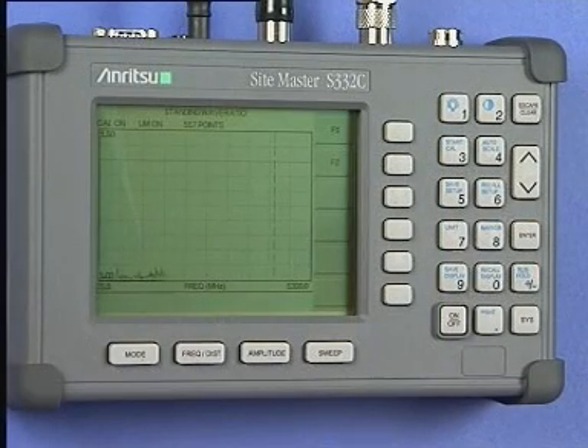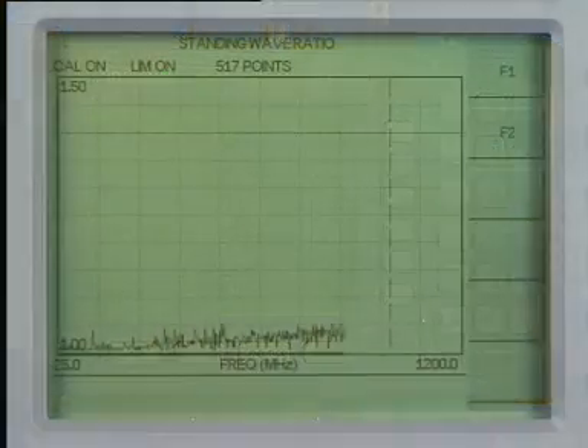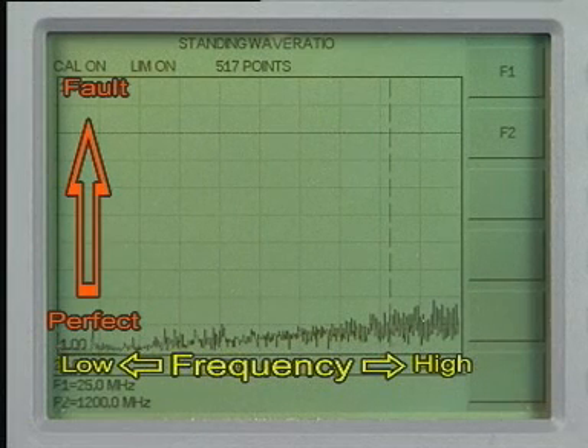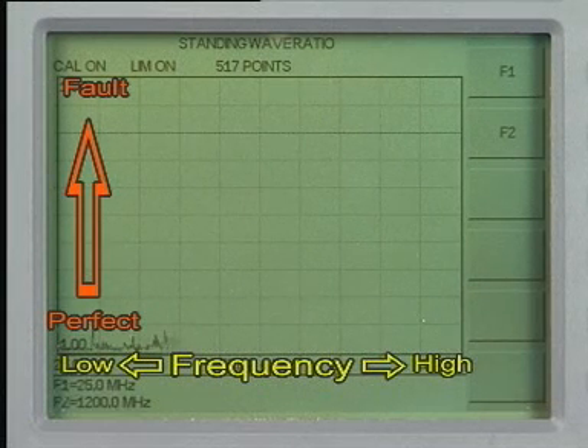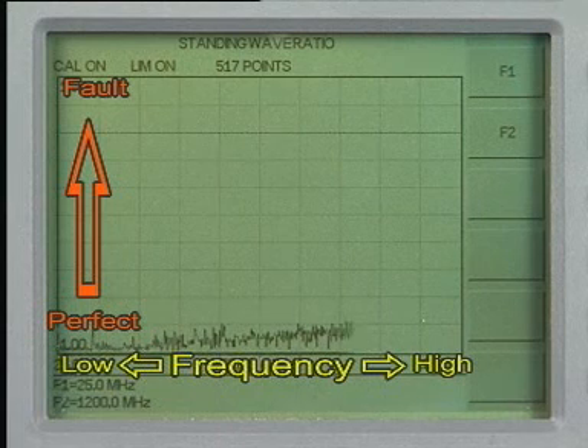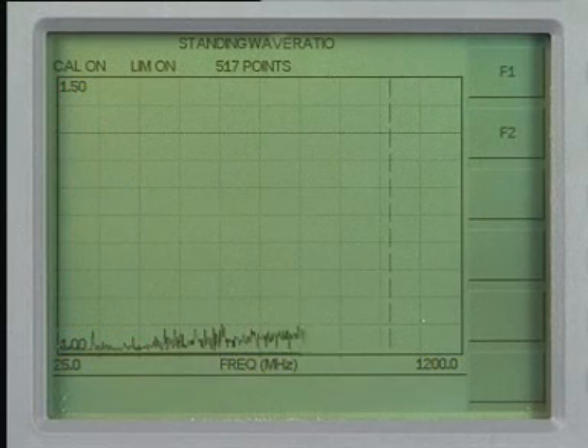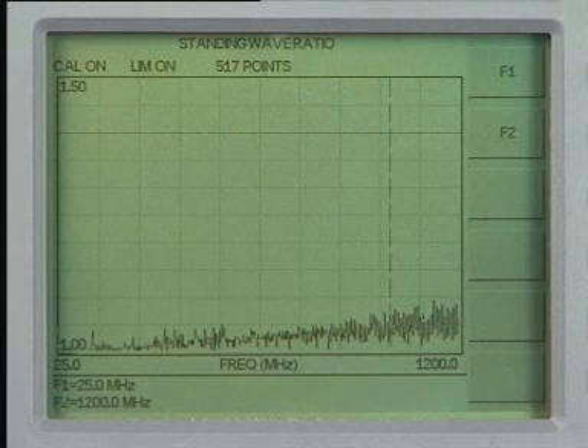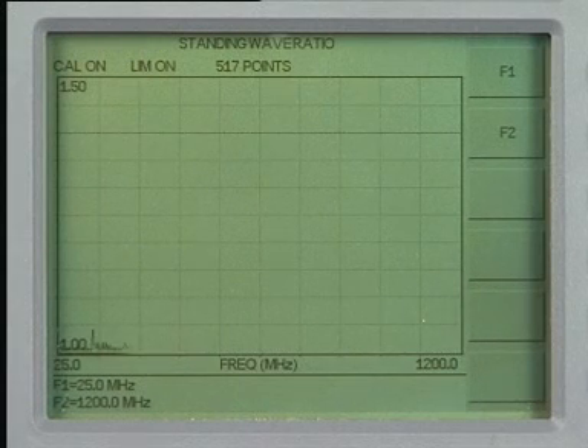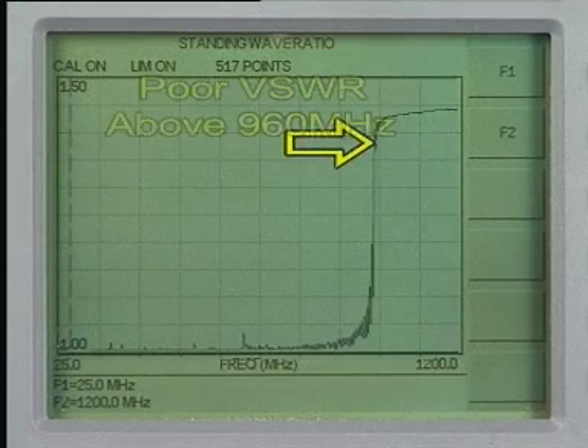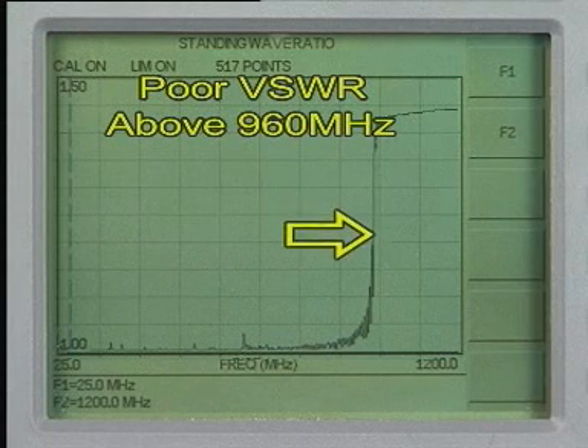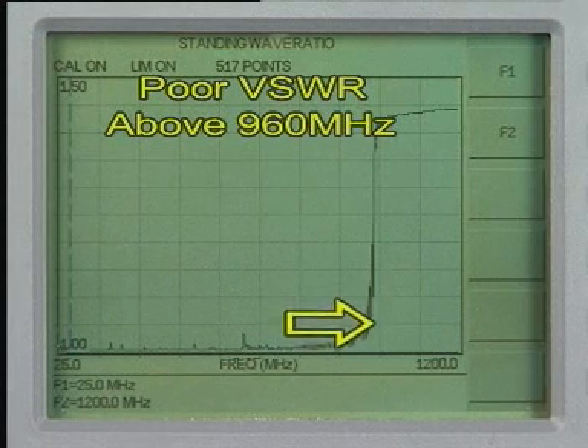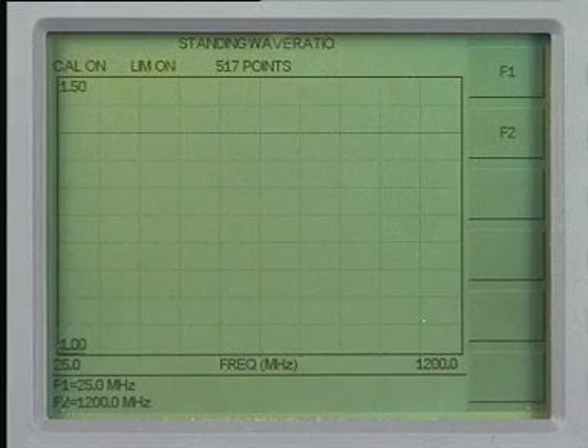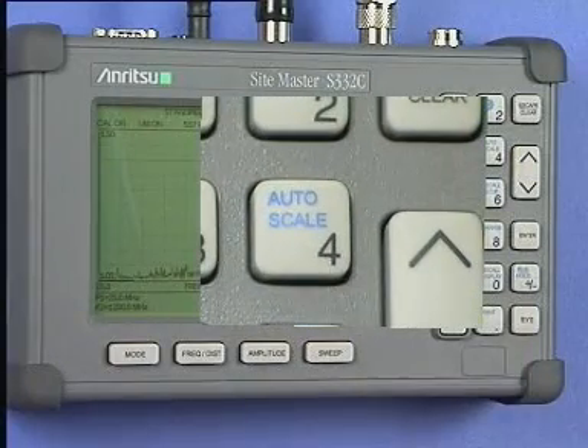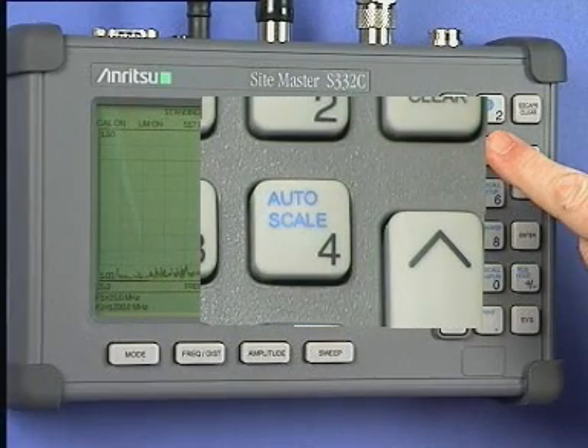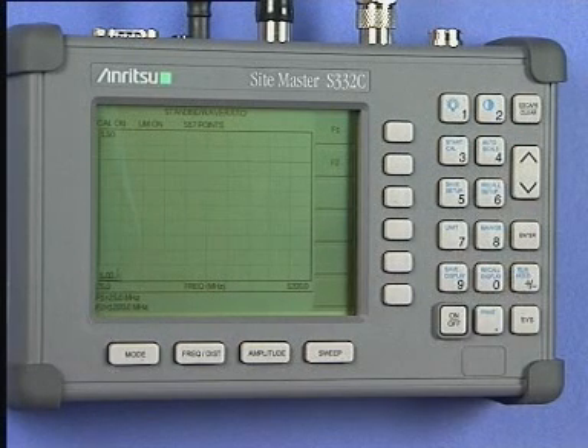The instrument will now sweep between the F1 and F2 frequency limits and display in graphic form the VSWR level or the return losses. In our example, we have selected VSWR and we see that there is nothing wrong with our antenna system. An elevated reading indicates a high VSWR. The Auto Scale key will adjust the display graph vertical axis so it is best suited to the results you see on the screen.